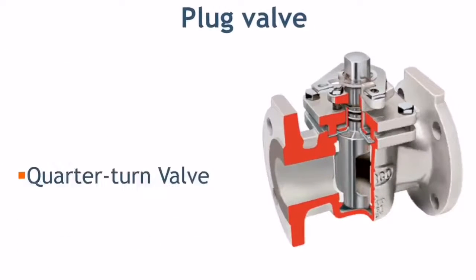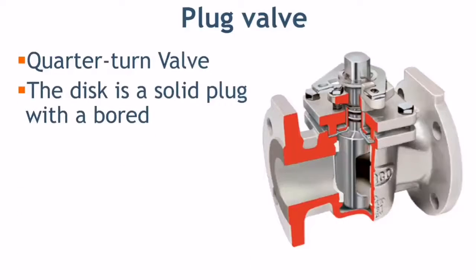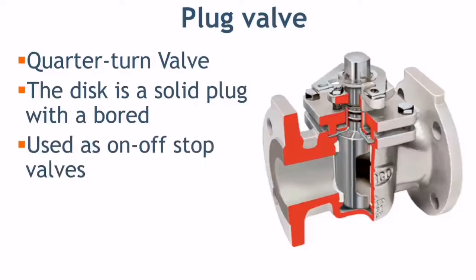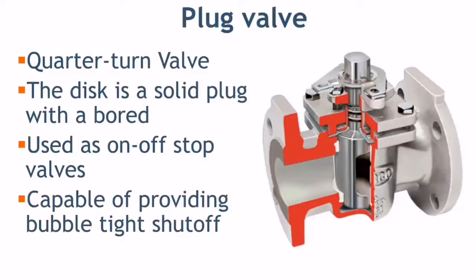Plug valve is a quarter-turn rotary motion valve that uses a taper or cylindrical plug to stop or start the flow. The disk is in a plug shape which has a passage to pass the flow. Plug valve is used as an on-off stop valve and is capable of providing bubble-tight shutoff. Plug valve can be used in vacuum to high pressure and temperature applications.